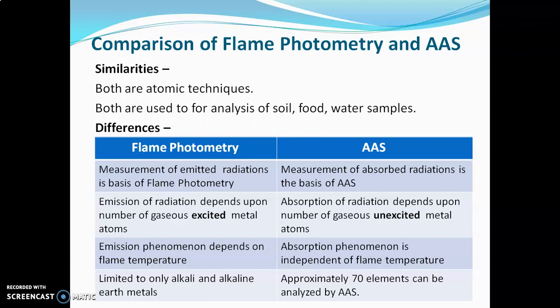Regarding differences: in flame photometry, measurement of emitted radiations is the basis, whereas measurement of absorbed radiations is the basis of AAS. Emission of radiation depends on the number of gaseous excited metal atoms, while absorption of radiation depends on the number of gaseous unexcited metal atoms. Emission phenomena depend on flame temperature, while absorption phenomena are independent of flame temperature. Flame photometry is limited to alkali and alkaline earth metals, while AAS enables analysis of approximately 70 or more elements.